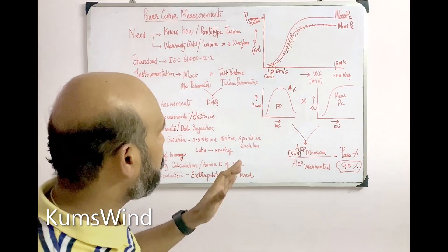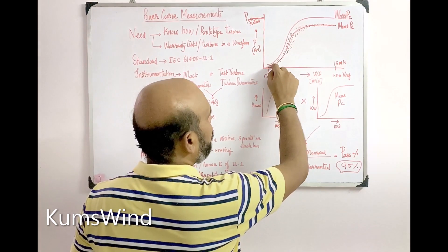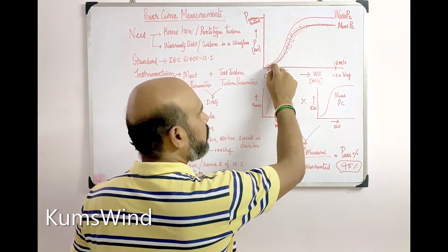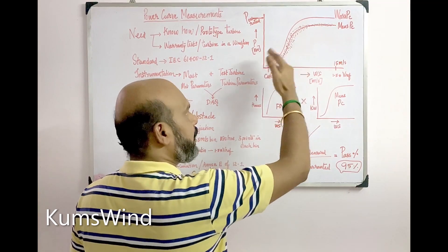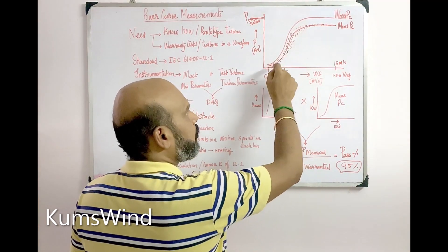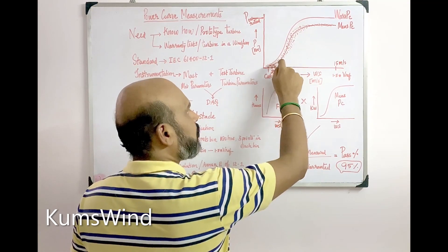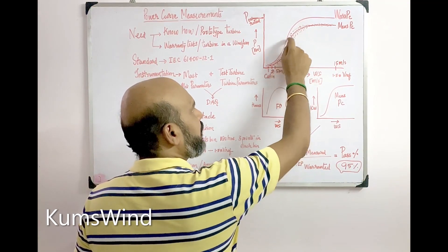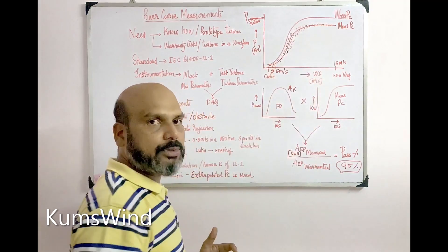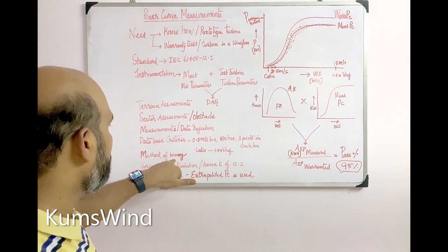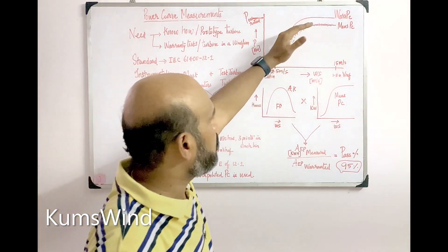The method of binning is similar to an averaging process. For every bin you calculate an average point — you should have a minimum of three data points per bin, but you can have any number more than three. All these average points are joined together to finally produce the binned power curve. This process is explained in the 'Method of Binning' section of the standard.